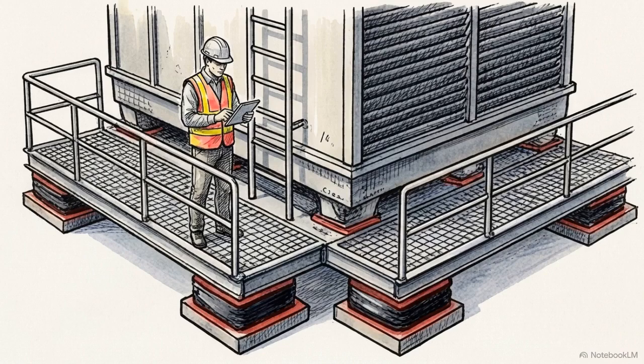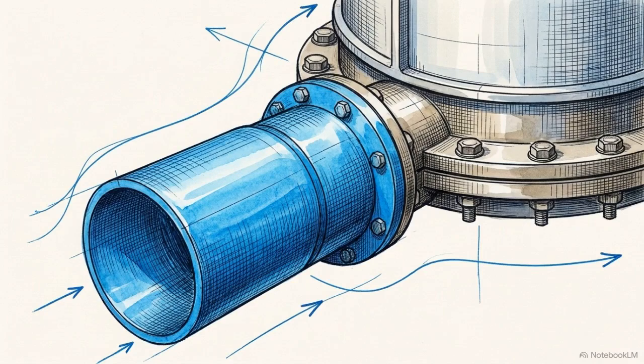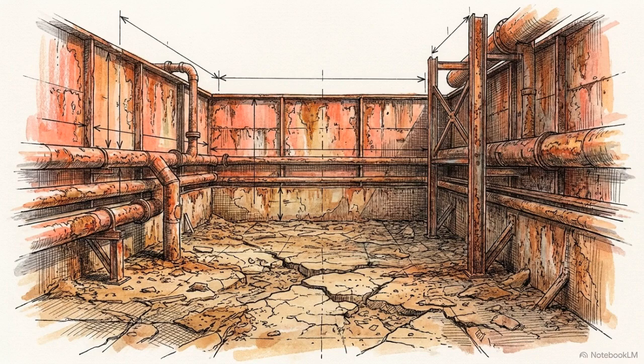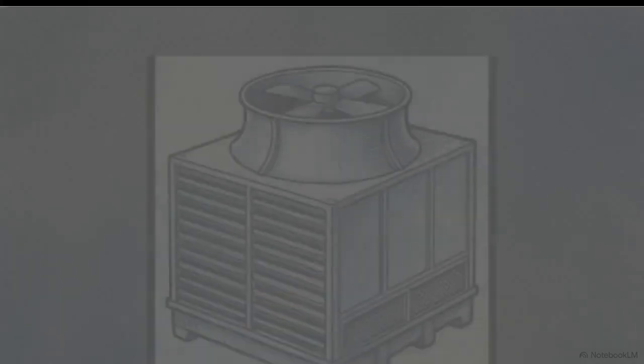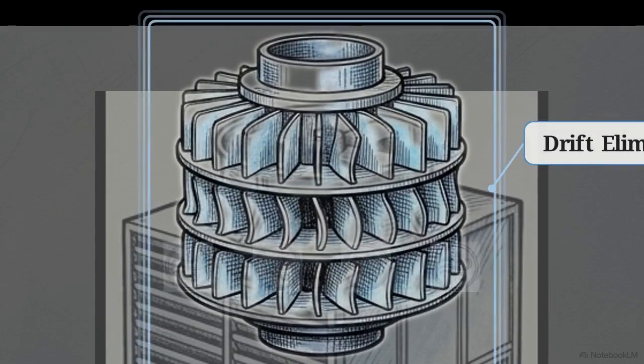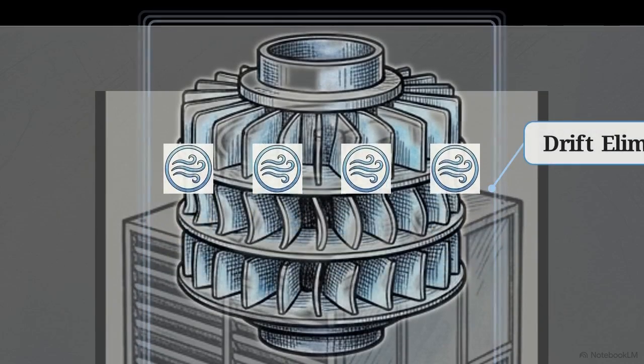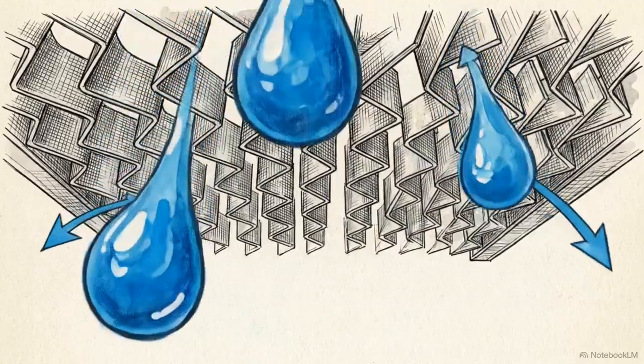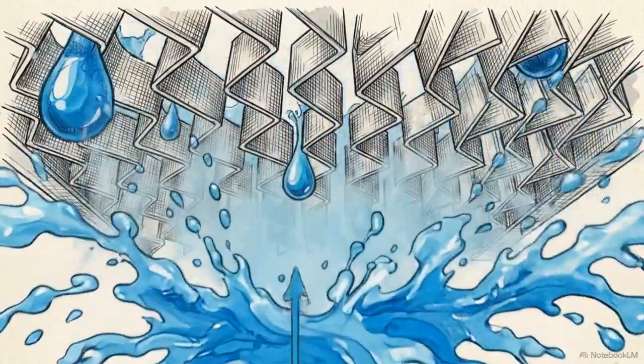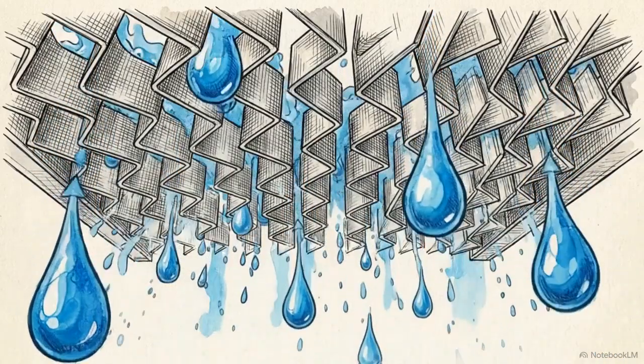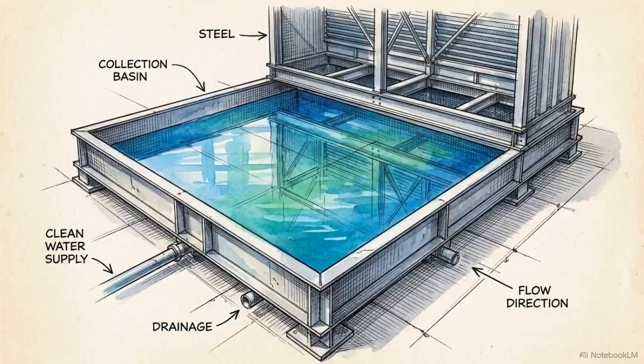physically possible. Step 4 is securing the water loop, which starts by connecting an uninterrupted makeup water line and performing your preliminary leak checks. If a leak drains the system and forces the cooling tower to operate in a dry mode, it can crash the entire facility. To keep water in the system, we use a component called a drift eliminator, located right at the top discharge area of the tower. The drift eliminator catches escaping water droplets mid-air, forcing them to collide against the slats and dropping them safely back down into the collection basin. This aggressive level of water management prevents sudden system crashes and saves thousands of gallons of operational water over time.